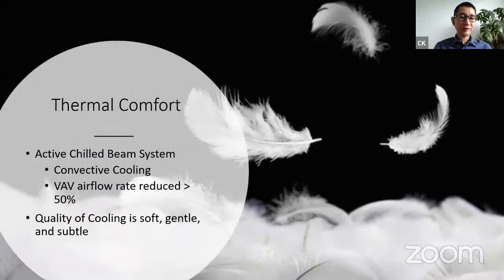In terms of thermal comfort, the active chilled beam system is convection cooling, right? It's not forced air. So the VAV airflow rate is reduced by at least 50%. We do not get the harsh cooling of a conventional air conditioning system, where the airflow is blown at our body at high air speed. So you hardly feel the airflow at all, but you feel the cooling. The quality of the cooling is very soft, very gentle, and quite subtle.